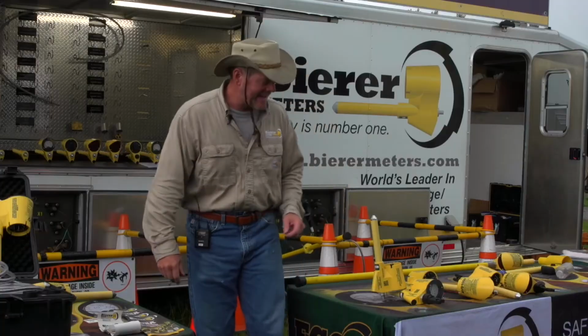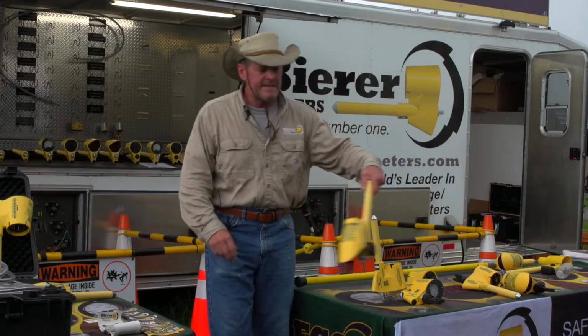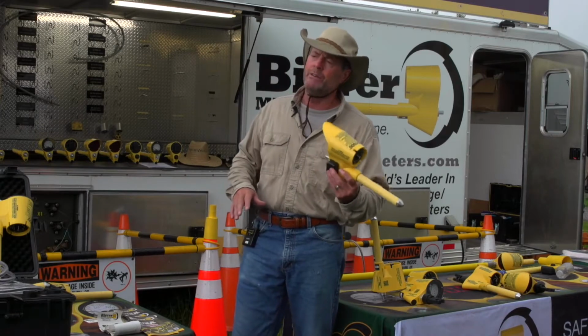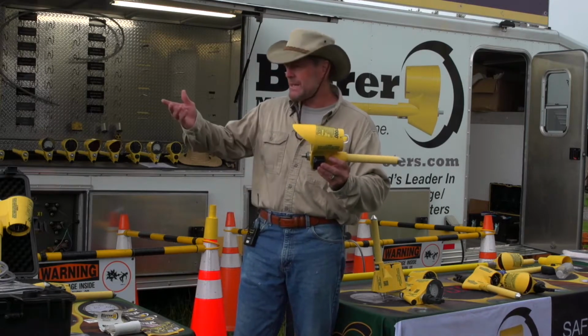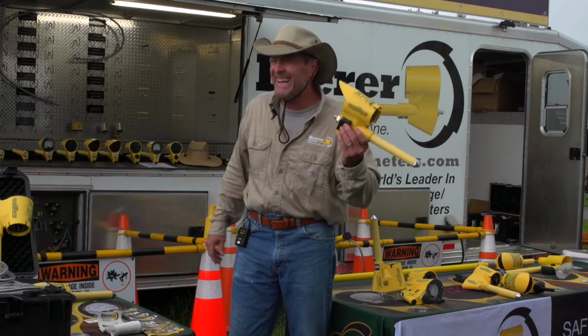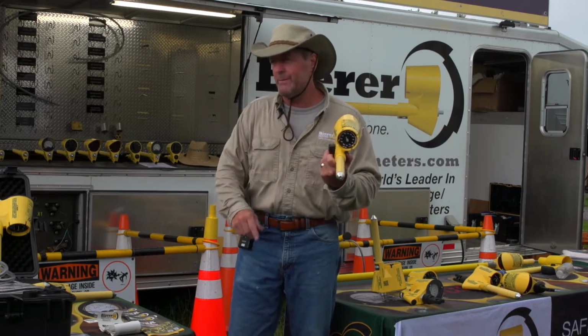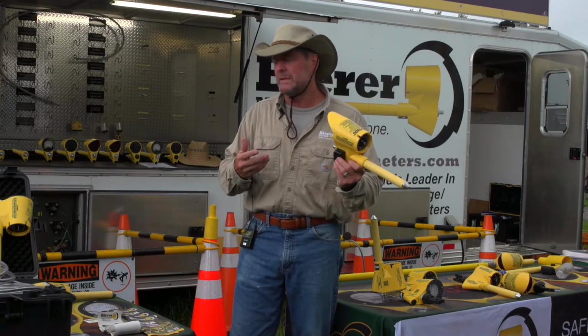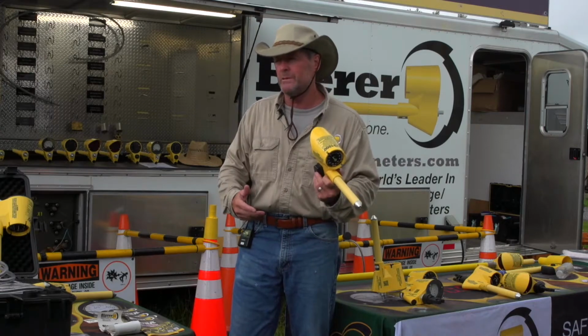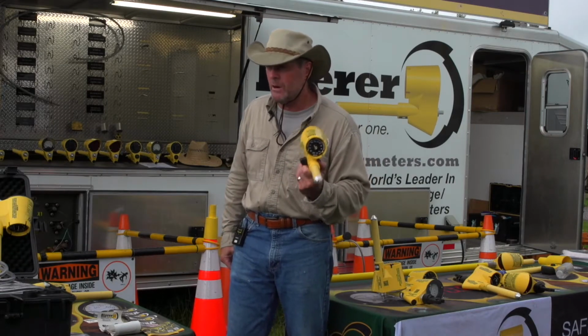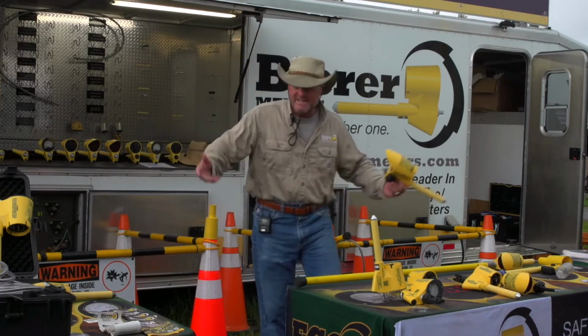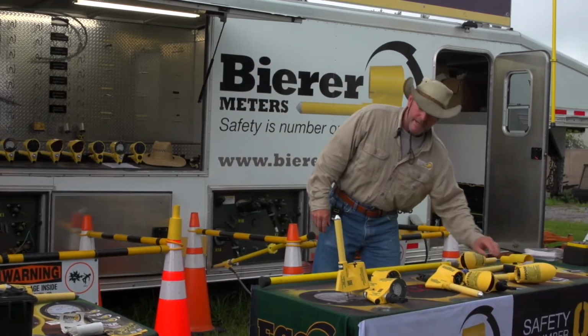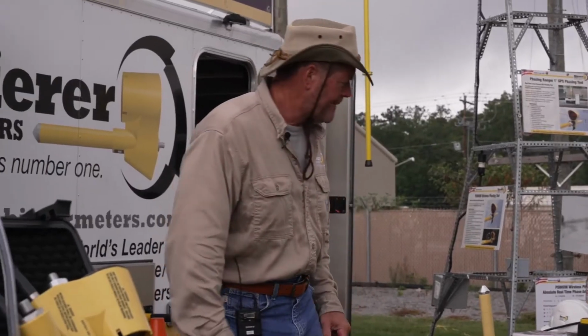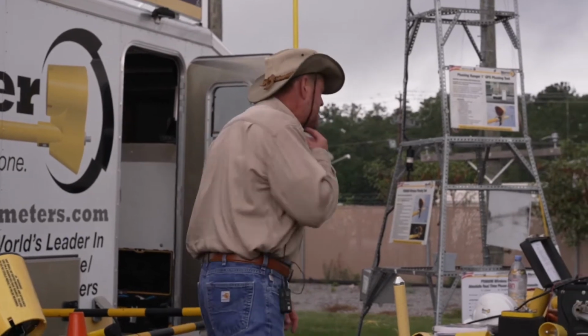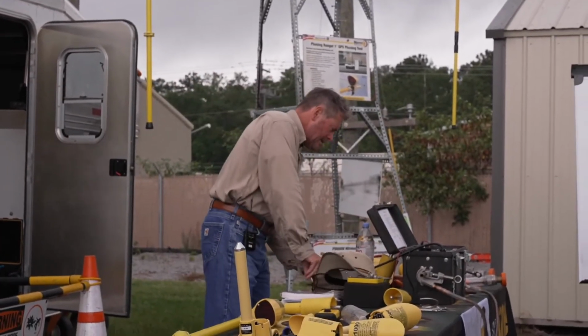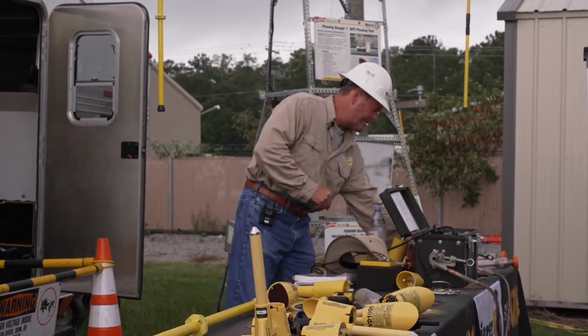That's how they work. So if that's the case, because it's giving you a voltage indication, or you're verifying you're in phase, out of phase, the components are energized like Ryan said, that means the tool's to be considered energized. Because of the resistors, you don't have the primary power coming through these tools, obviously, but they're still energized with quite a bit of voltage. So you need to treat these tools as energized, always as energized, okay? That's how they work. Okay, so we're going to talk about tool functionality, because now you know they're energized. So when you're working these tools, you're going to be working hot.